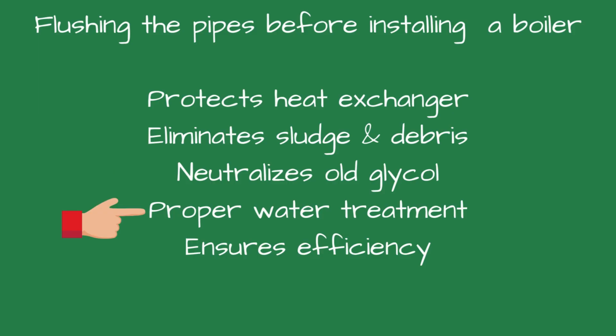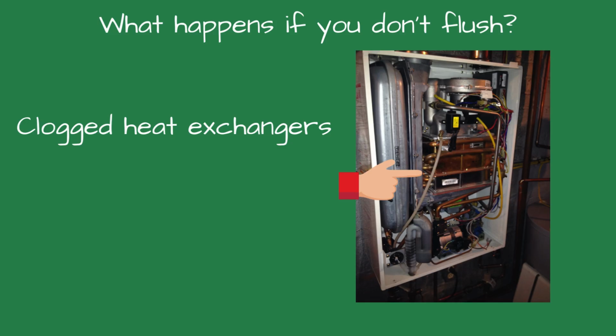Number 4, it ensures water treatment works properly. Adding glycol inhibitors or new glycol to dirty water is like painting over rust. Starting with clean water allows treatment chemicals to do their job effectively. Lastly, it ensures efficiency. Dirty or acidic water insulates surfaces, slows heat transfer, and wastes fuel. Flushing allows the boiler to operate at its rated efficiency. So what happens if you don't flush? Neglecting to flush before installing the boiler sets the stage for trouble.